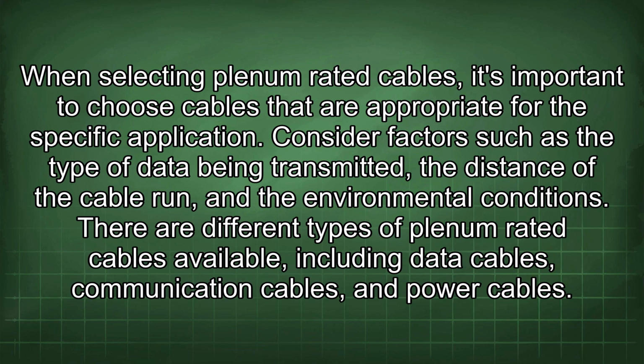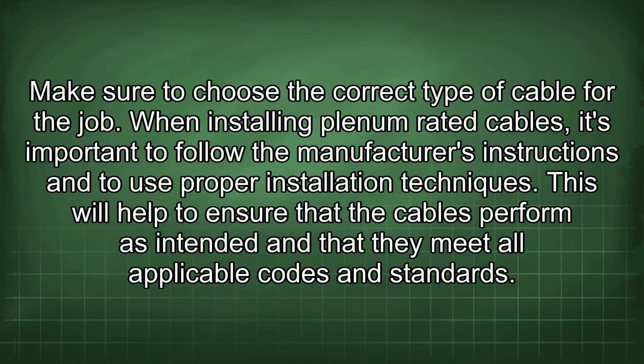Consider factors such as the type of data being transmitted, the distance of the cable run, and the environmental conditions. There are different types of plenum-rated cables available, including data cables, communication cables, and power cables. Make sure to choose the correct type of cable for the job. When installing plenum-rated cables, it's important to follow the manufacturer's instructions and to use proper installation techniques. This will help to ensure that the cables perform as intended and that they meet all applicable codes and standards.